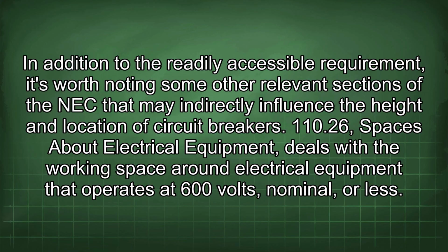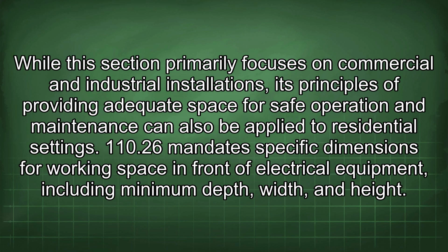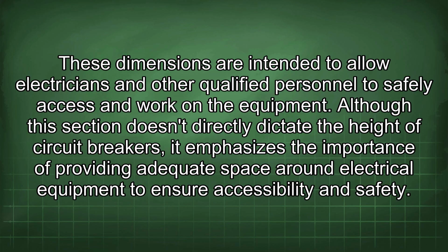110.26, Spaces About Electrical Equipment, deals with the working space around electrical equipment that operates at 600 volts, nominal, or less. While this section primarily focuses on commercial and industrial installations, its principles of providing adequate space for safe operation and maintenance can also be applied to residential settings. 110.26 mandates specific dimensions for working space in front of electrical equipment, including minimum depth, width, and height. These dimensions are intended to allow electricians and other qualified personnel to safely access and work on the equipment. Although this section doesn't directly dictate the height of circuit breakers, it emphasizes the importance of providing adequate space around electrical equipment to ensure accessibility and safety.